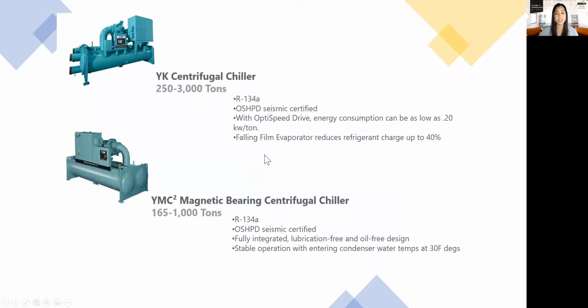Currently, you can still specify our trusty and reliable YK centrifugal chiller and our YMC2 magnetic bearing centrifugal chillers, since we've now clarified that R-134A will still be available for future servicing of these chillers. But in addition to that, York is also currently working with refrigerant manufacturers to see which next generation HFO will replace 134A as a drop-in for the YK and the YMC2 in 2024. So stay tuned and we should have that information as soon as we get it.